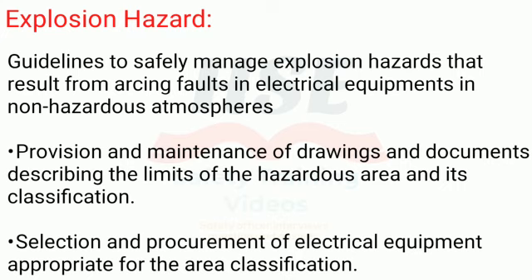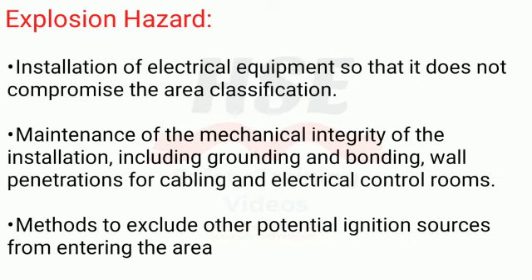Explosion hazard. Guidelines to safely manage explosion hazards that result from arcing faults in electrical equipment in hazardous atmospheres. Provision and maintenance of drawings and documents describing the limits of the hazardous area and its classification. Selection and procurement of electrical equipment appropriate for the area classification. Installation of electrical equipment so that it does not compromise the area classification. Maintenance of the mechanical integrity of the installation, including grounding and bonding, wall penetrations for cabling and electrical control rooms.